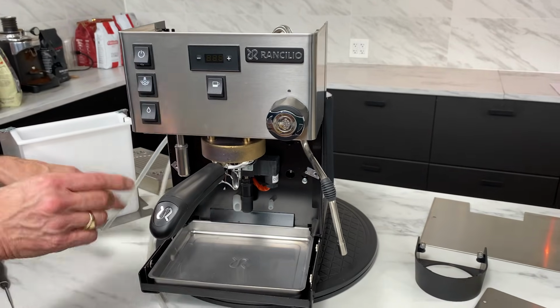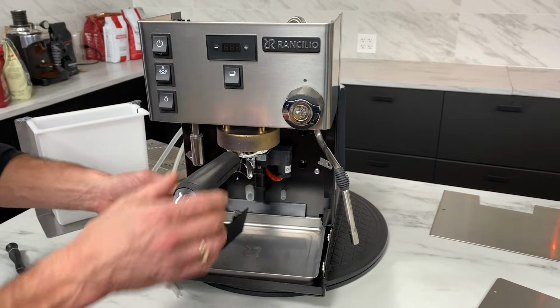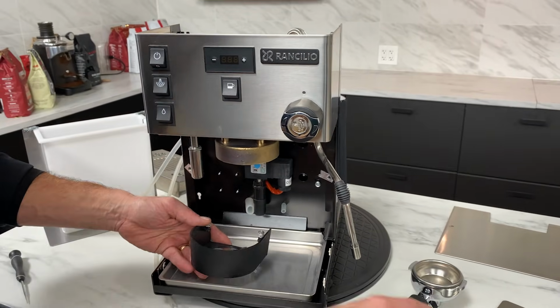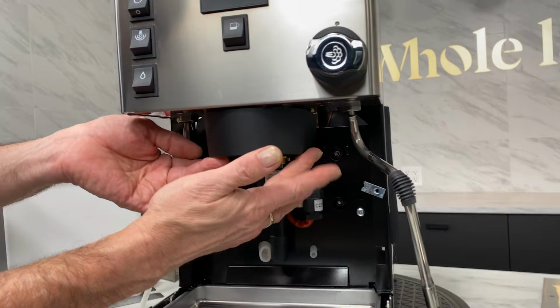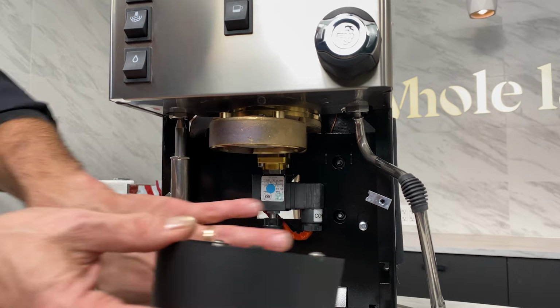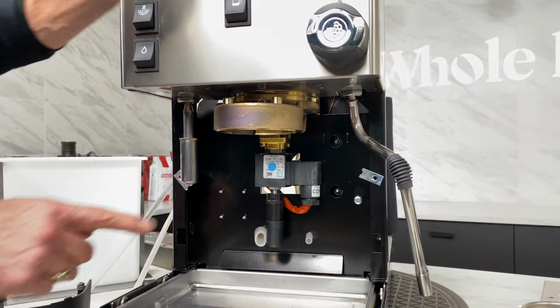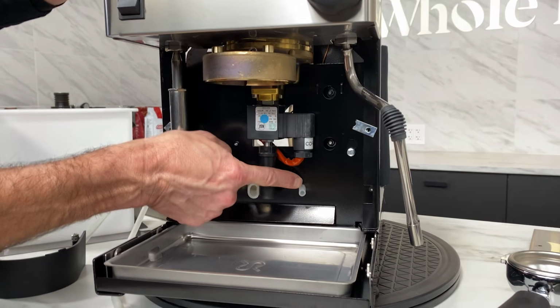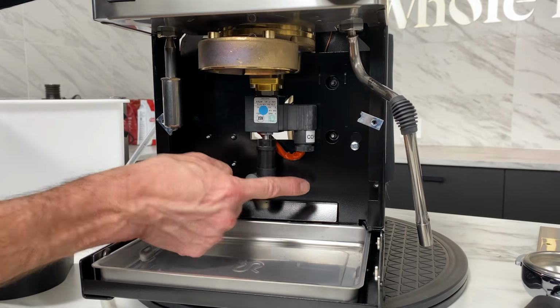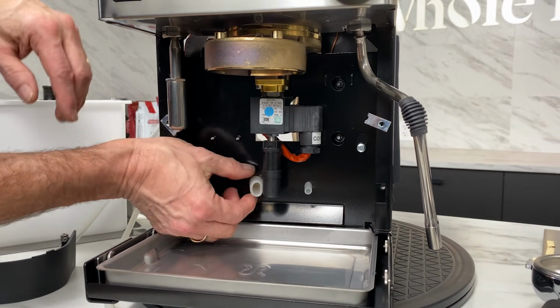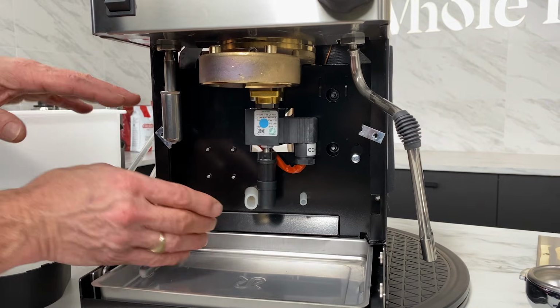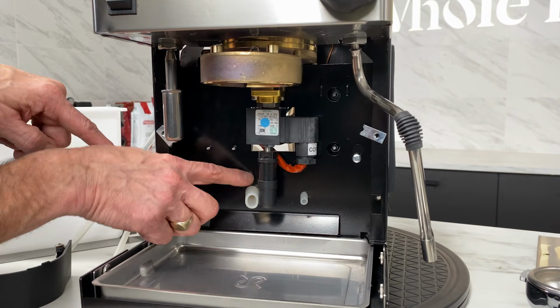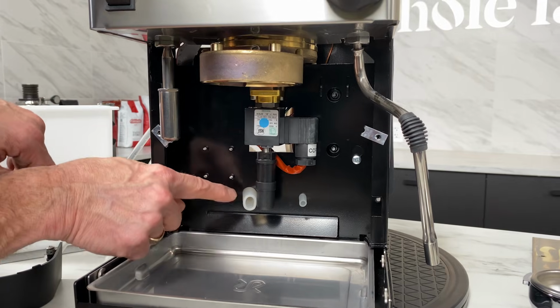Okay, out front. So I've taken this cover off. So this usually sits here. I'll take the portafilter out. So this is a group head. So that cover would generally be here. I've also taken the cover off the front here so you can see back in here. Now here's where that vacuum relief valve drains, and here's where that safety valve, should it go, again, that's probably never going to happen, but if it did, all that water is going to end up outside into the drip tray.